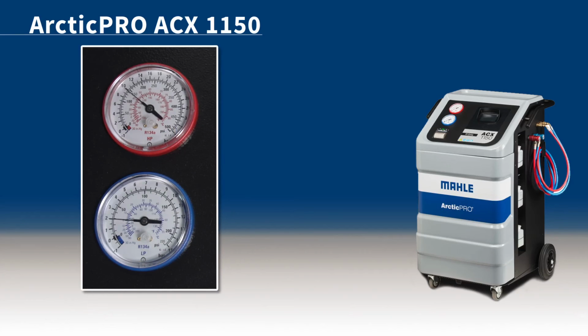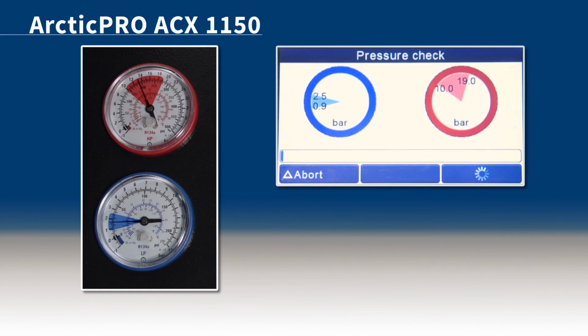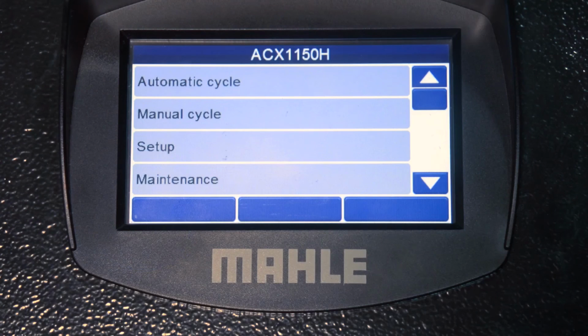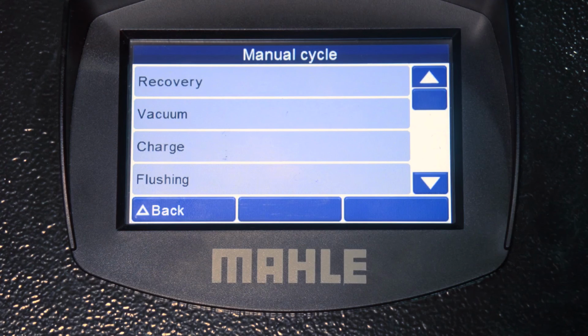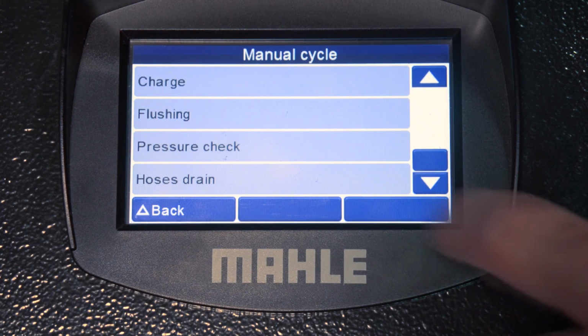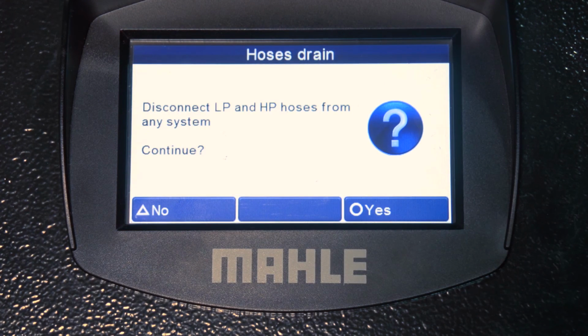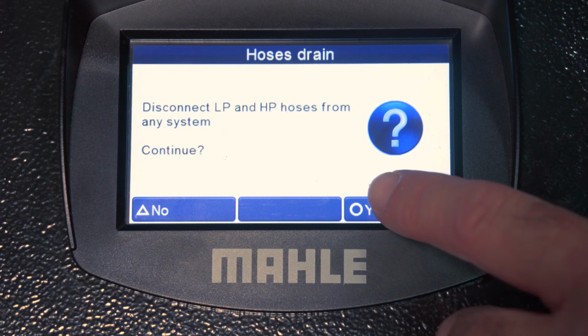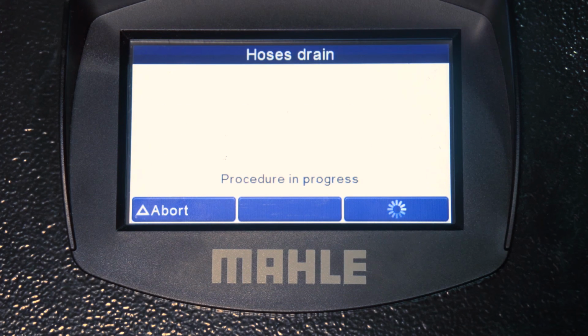At the end, check that both values on the HP and LP gauges fall between the values shown on the display. To clear pressure from the inside of the unit hoses, in the manual cycle, use the up or down arrow keys to select Hose Emptying, and then press Enter. Allow the procedure to run to completion.